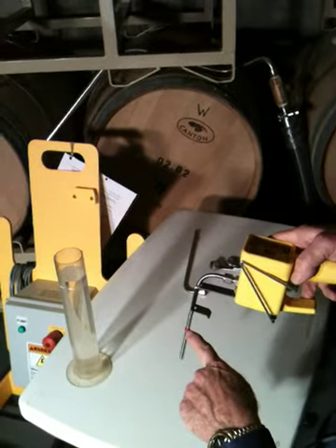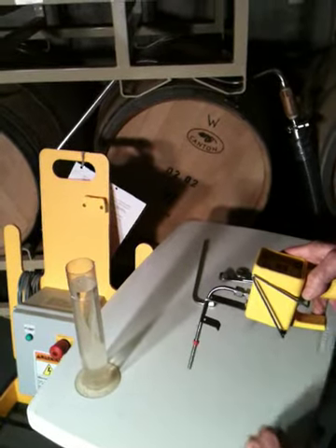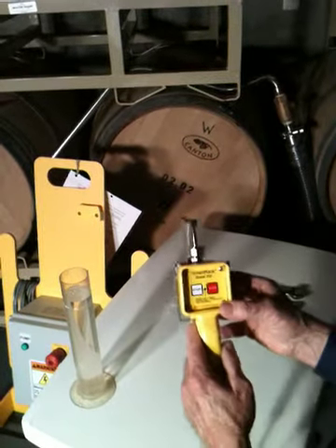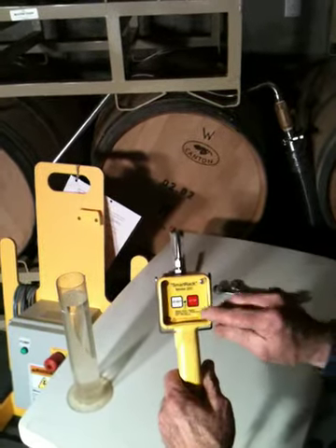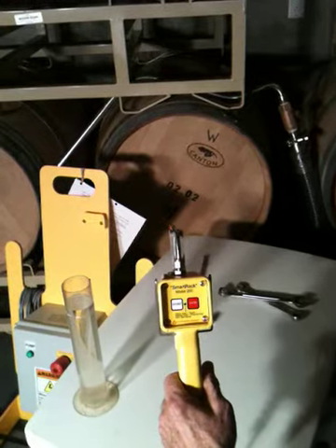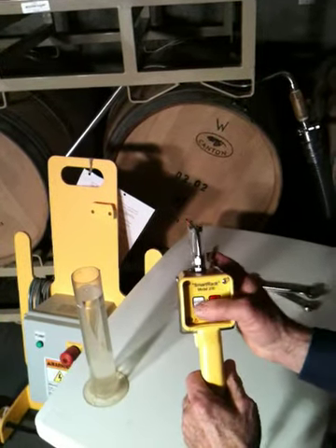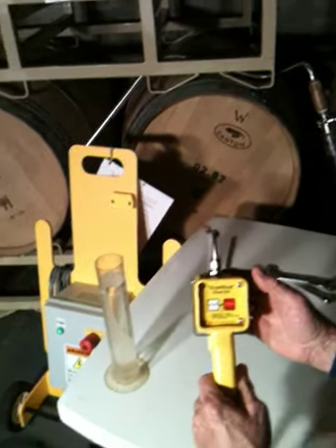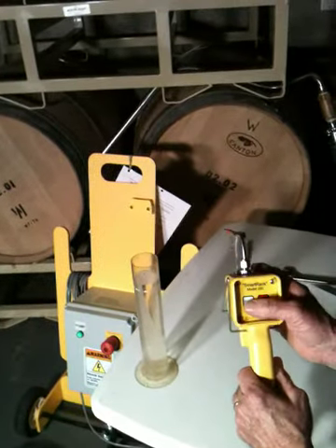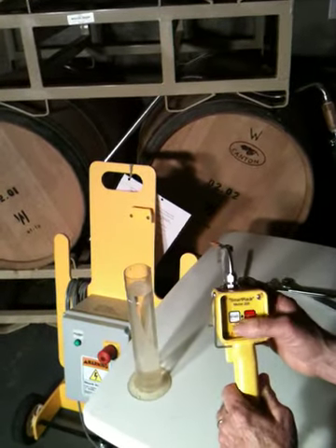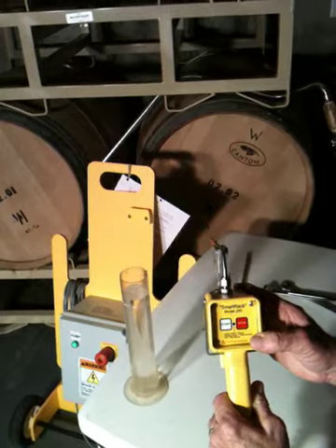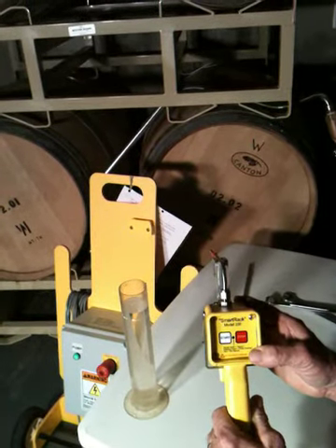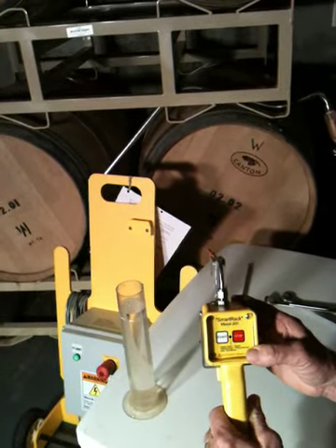So now we want to start the calibration mode and make sure that it operates when the water level reaches the red band. In order to enter the calibrate mode, you see we have power applied. A little LED light is steady green. That tells you that it's ready to operate. If I hit start, it turns on. The little green pump light comes on. I hit stop, it goes off again. But while it's running and start, you notice the LED flashes 1 cycle per second to let you know that the pump should be running.